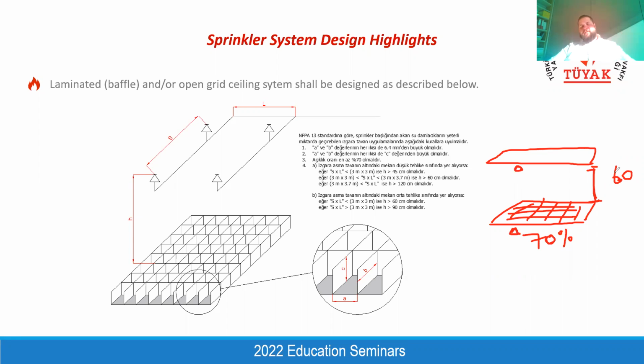And if you are fulfilling both of the requirements, and the open grid ceiling physical requirements, and I will explain, the distance between the laminated baffles shall be not less than the depth of the grid ceiling. It is the issue about the water to be reached beneath the ceiling. If you have very high profiles, then the water will not reach the floor level, and the fire will not be taken under control.